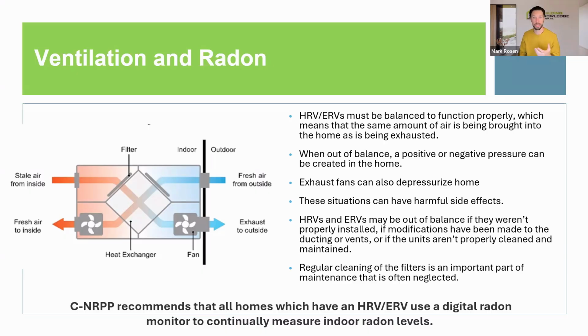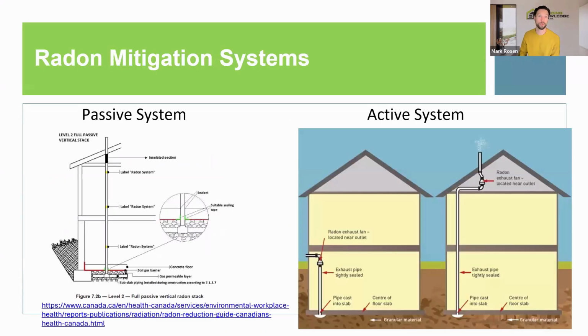A ventilation system that is properly balanced is key here. By balanced, I mean the flow of air in and out of the home has to be equal, so you're not generating pressure with your continuous solution. If you have an imbalanced solution that generates negative pressure, you may actually draw radon into the home. So commissioning your equipment is key. Installers that install ventilators should be balancing and testing them, and applying a label stating the flow rates they've been balanced at, so you know you can rely on it alongside your passive and active radon systems as part of your overall radon control strategy.